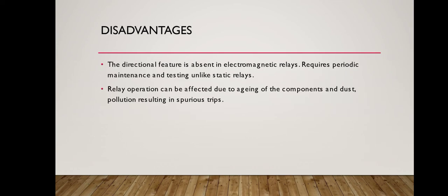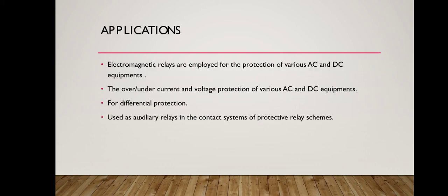Then we will see the disadvantages of relays. The directional feature is absent in electromagnetic relays, and they require periodic maintenance and testing, unlike static relays. Relay operation can be affected by aging of the components and dust pollution, resulting in spurious trips.